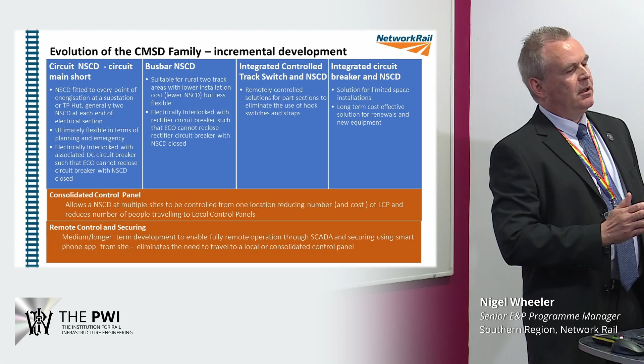So we started off with just the NSCD, which is fitted to every electrical section at a substation or TP hut. Over time we've developed the tools in the toolbox, so we've now got the busbar short circuit device, which means we only need to fit one per site rather than 4, 8, or 12, however many tracks there are. So in terms of equipment and installation, it's a lot quicker.